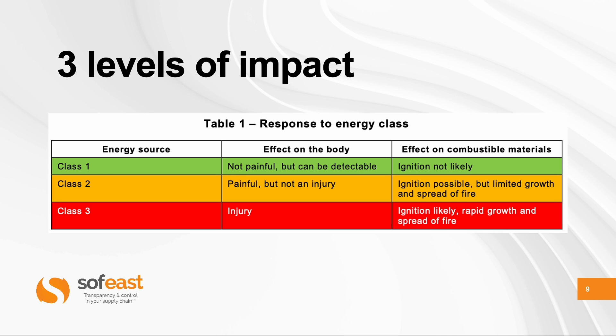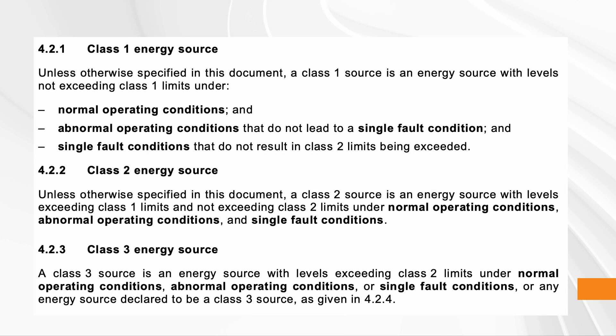Now let's talk about the impact of hazards. There are three levels: Class 1, Class 2, and Class 3. Class 1 is basically not really an issue — no real danger to the body in terms of injuries, and no significant fire risk. Class 2 is painful but not an injury — meaning you don't need to go to hospital or see a doctor — and there might be a small fire. Class 3 is very high severity: injury requiring hospitalization, possible death, or a large fire.